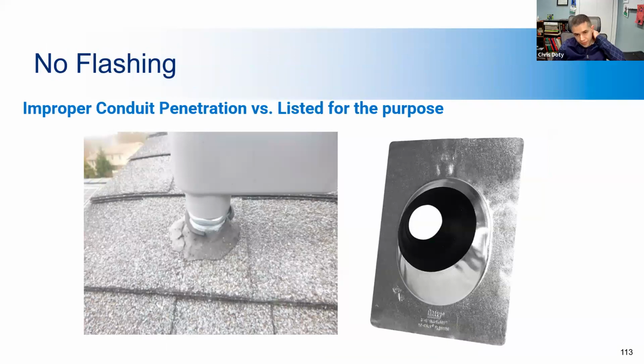So here we have a situation where this roof penetration was not properly sealed. The contractor drilled through the roof, and then rather than sealing it properly, which you would use this piece of equipment to do, as we saw earlier, they used what's called duct seal, or sometimes called dum-dum, to seal the opening. It doesn't look great, and it's basically putty that goes around the hole. It's somewhat weatherproof, but it's not being used correctly here. It shouldn't be used permanently for this kind of application.